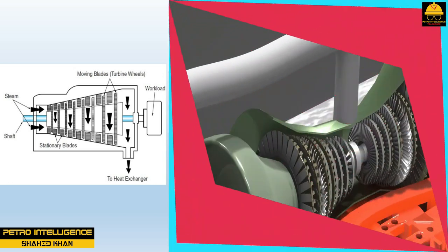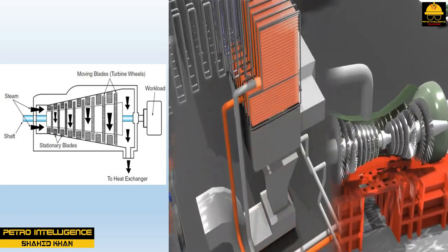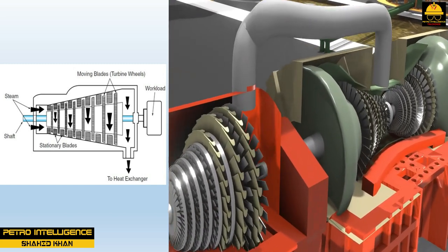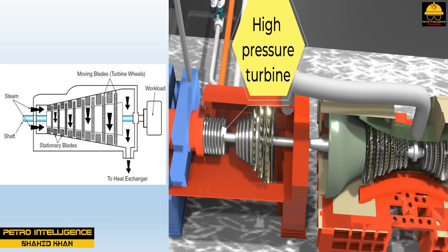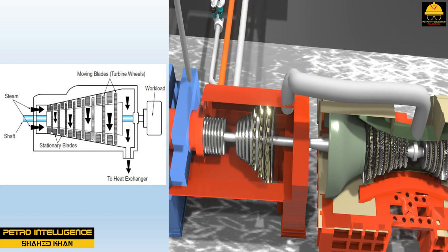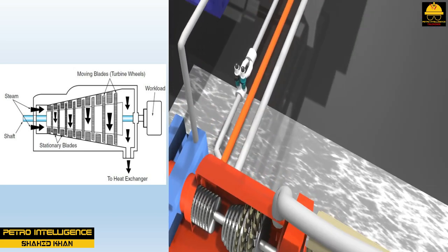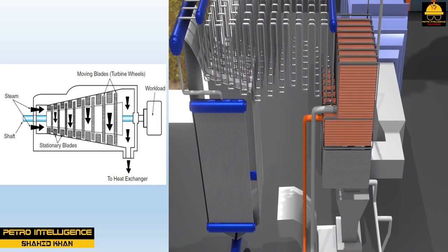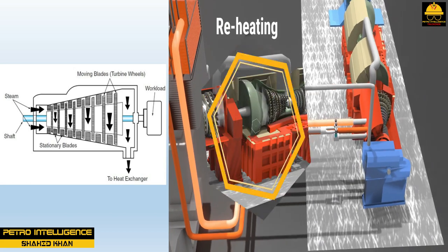The amount of steam energy needed to perform useful work depends on the pressure range through which the steam expands. The steam used to operate a steam turbine is produced in a boiler. Boilers produce steam that can enter a turbine at temperatures as high as 538 degrees Celsius — or average 1000 to 1050 degrees Fahrenheit — and pressures as high as 3500 PSI inlet and 200 PSI outlet. Steam turbines can also run under a vacuum. High pressure steam is admitted slowly to warm the turbine and remove condensate. Steam turbines are used to drive electric generators in modern power plants, and a multi-stage steam turbine is considered one of the world's most powerful engines.